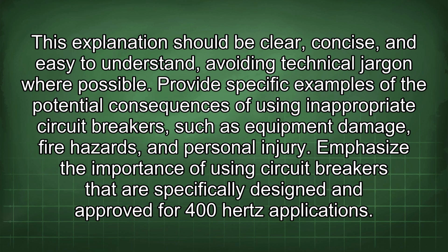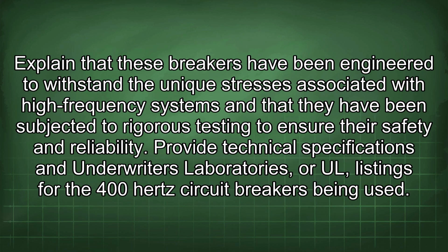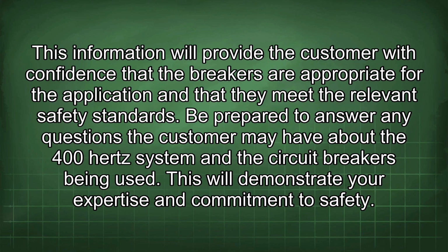Emphasize the importance of using circuit breakers that are specifically designed and approved for 400 Hz applications. Explain that these breakers have been engineered to withstand the unique stresses associated with high-frequency systems and that they have been subjected to rigorous testing to ensure their safety and reliability. Provide technical specifications and Underwriters Laboratories, or UL, listings for the 400 Hz circuit breakers being used.